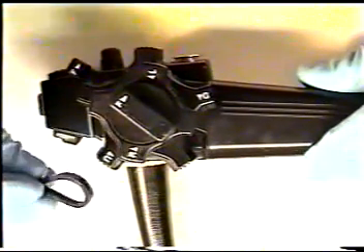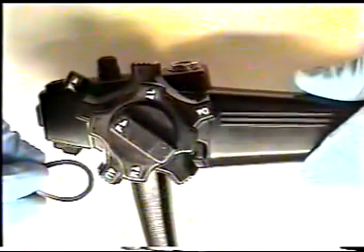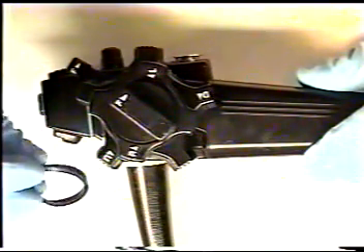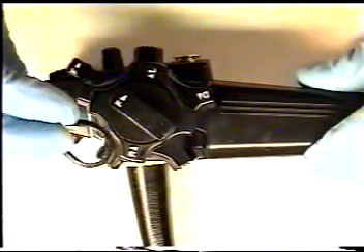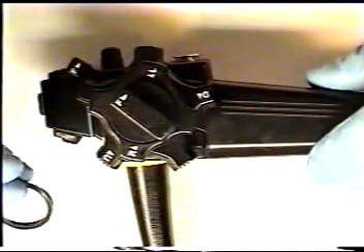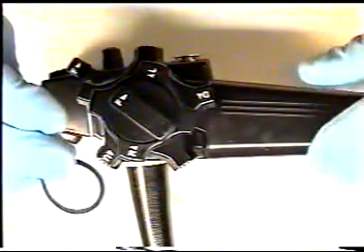When disassembling the up, down, left, right lock knob assembly from the body, it is best to take off each piece one at a time, laying it on your work area in sequence. So when we reassemble the up, down, left, right lock knob assembly, we can reassemble back in sequence with the parts starting from beginning to end. First, we have the left-right trim ring.